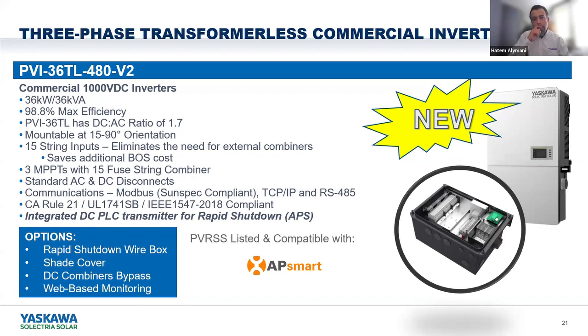Another thing worth mentioning is that all these inverters are mountable from 15 to 90 degrees in rotation. We also have a roof mounting kit that will allow you to put the inverter on the roof at a tilt angle. Of course, if you are putting the inverter on the roof and it's exposed directly to sunlight, then you would want to get a shade cover to reduce the temperature of the inverter and avoid derating of the production, because the inverters are going to protect themselves and throttle down if the temperature exceeds the safe limits.